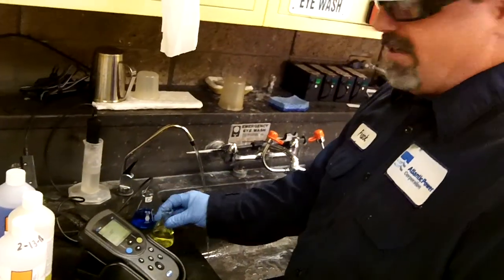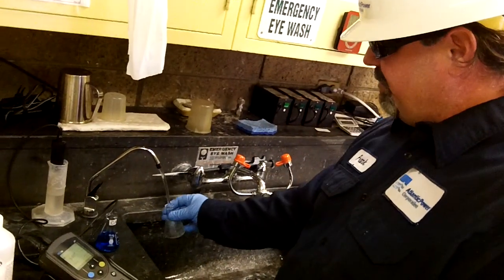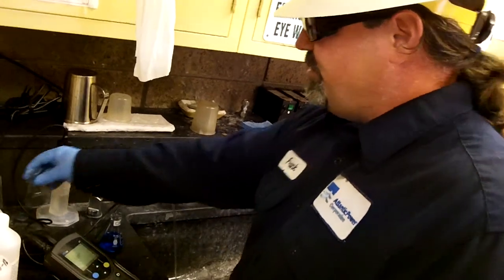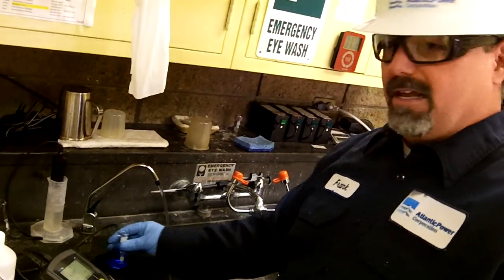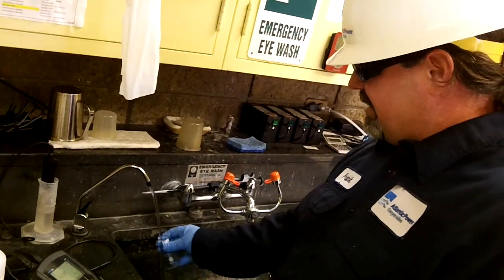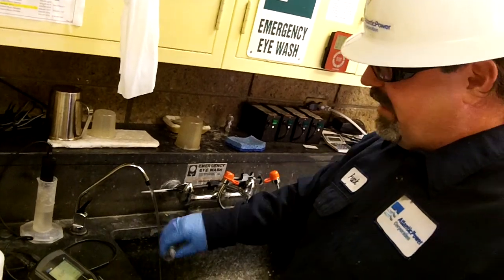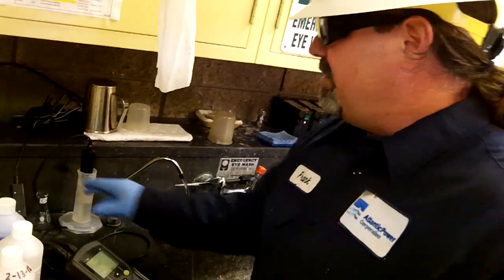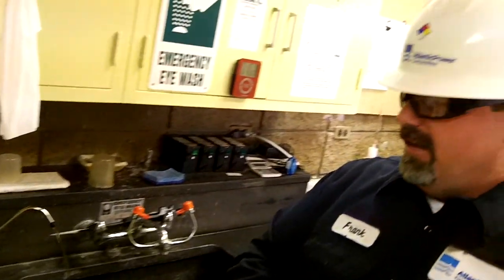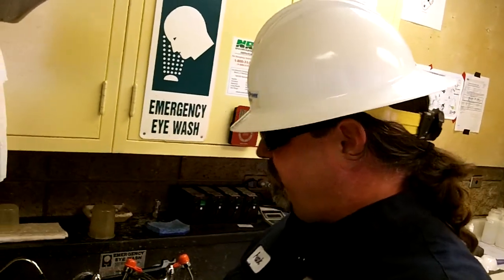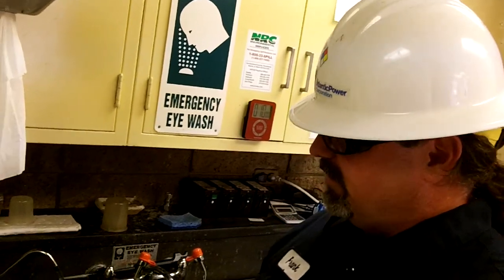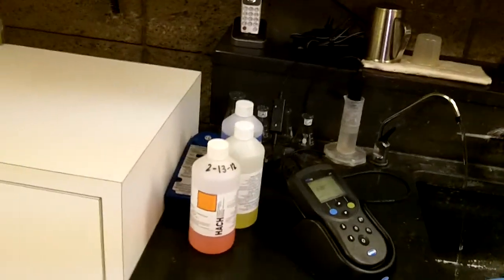That way somebody doesn't come along and try to cal the meter with storage solution that's been with the buffers that have been sitting for a long time. Because as I said, if the buffers sit open for any length of time, they're going to dissipate and they're not going to be accurate, and you're not going to get accurate calibration. So when you're done doing your cal, dump your buffers out, clean the bottles, and put everything back where they go. Okay, that's it for pH calibration. Thank you.